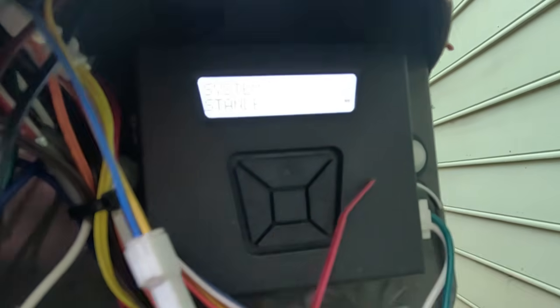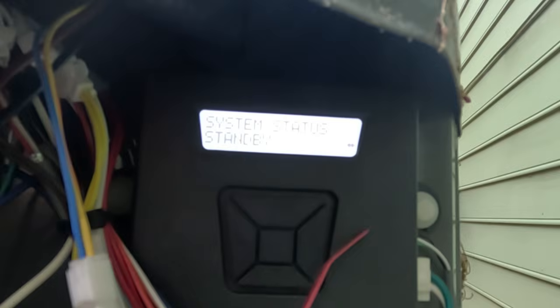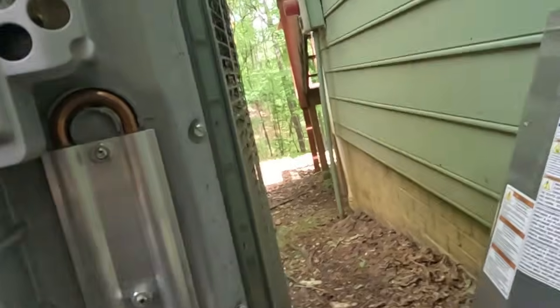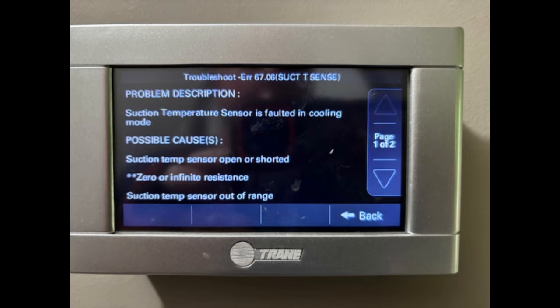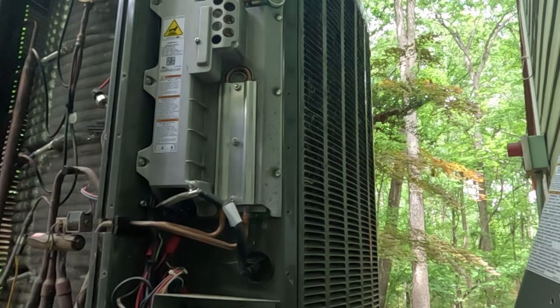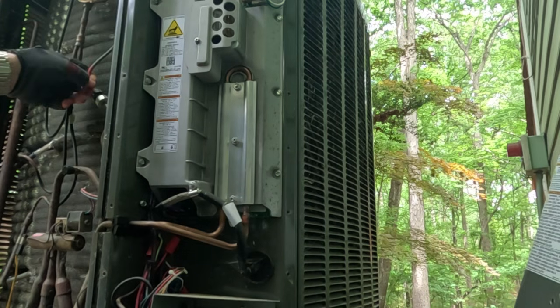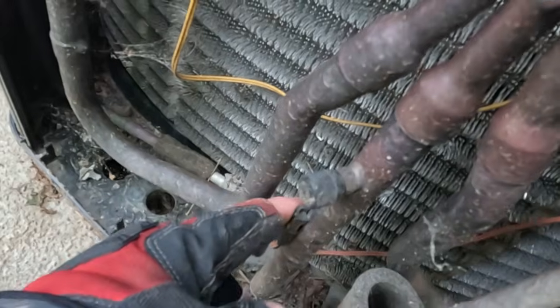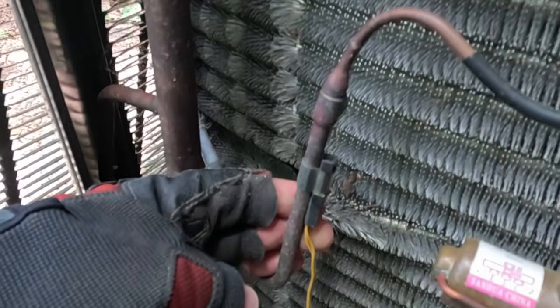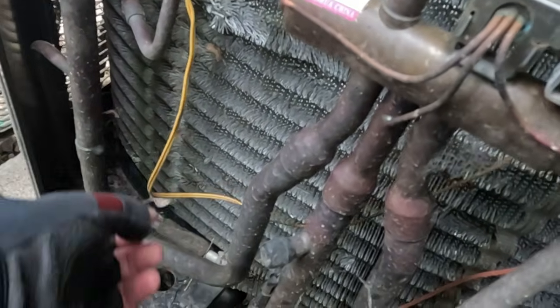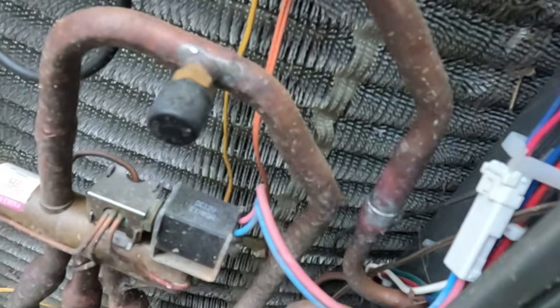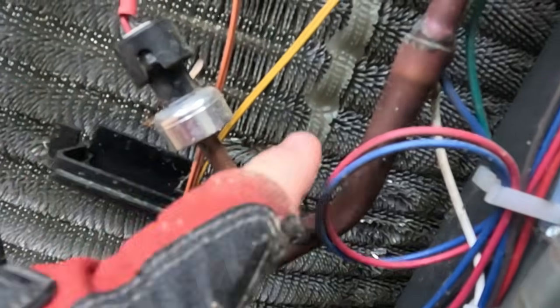But look right there. I can get the light to come on here, and we'll see if our fault code alert, if you can see that or not on the screen right there. Another infamous temperature sensor problem. So let's test it and see what it is. It's related to this one, suction line temperature sensor. Then your coil temperature sensor is over here, and that comes into play obviously for your defrost cycle. This particular model XV system also has a liquid line sensor on it. It has a pressure transducer for the high side and the low side.